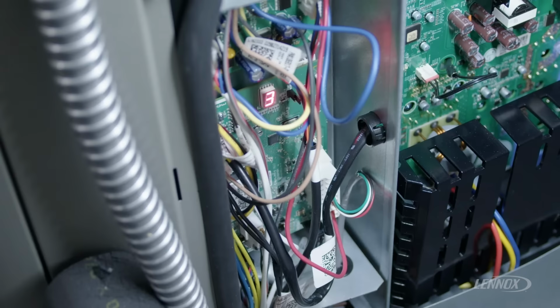Today we're going to cover error code E434. It simply reads communication error between unitary control and inverter control, which are the boards on the left and right respectively. The way these units operate is that the board on the left, our MUC, or modulating unitary control, wants to be in constant communication with the larger inverter control on the right.